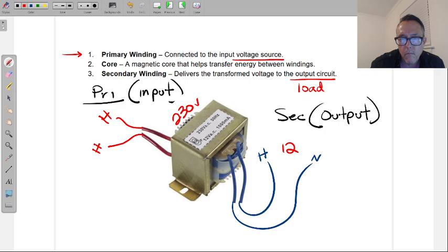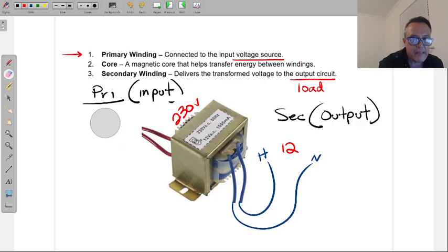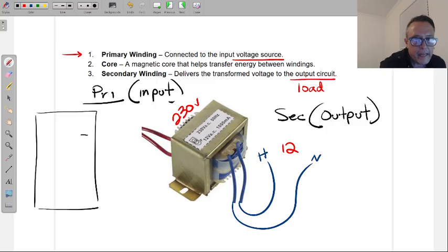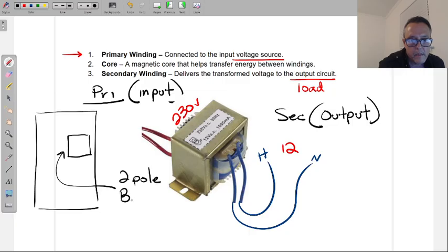And those two hots, are they from the same circuit? Yeah, right, they're from the same wire. So these two hots over here - if I'm going to connect it, I just grab the other hot? Yes. So the way we'd connect this, let's say we'd find a panel, and we'd need a 2-pole breaker. This breaker would be what we call a 2-pole breaker - it provides both phases, A phase and B phase, and we'd run one to one side and one to the other.